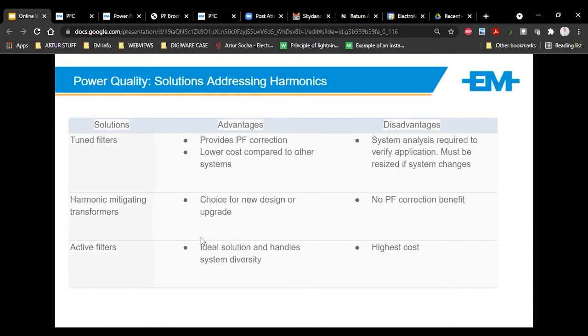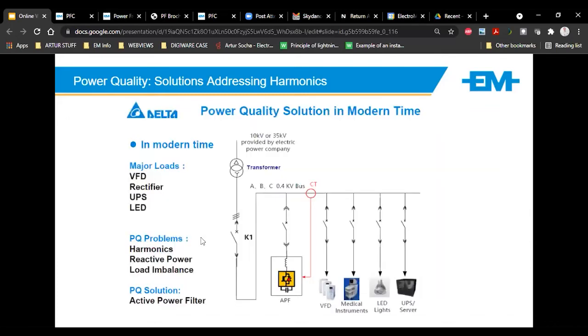An active filter works in real time to counter the harmonic. So it becomes capacitive and inductive in real time. Just an example of an active filter: I've got all my noise downstream, VSDs, LEDs, UPSs. I've put an active filter in line. It measures and it switches to counter those effects. Now, some utilities may have some sort of penalties if you inject high enough harmonics back into the grid. It depends on the council. A good example are solar plants.